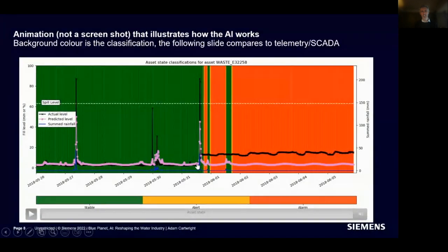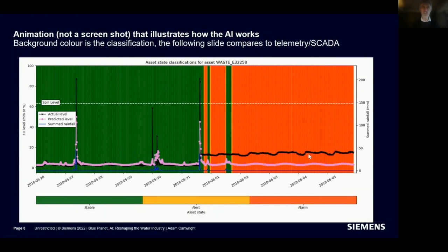But what happens after this rainfall event is that something caused a change in the baseline. The AI flagged this raised baseline. At the point where it starts to rain again, it considered whether there was a potential issue, and confirmed yes — there continues to be a challenge.